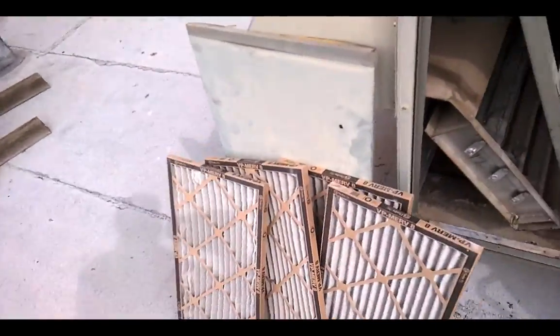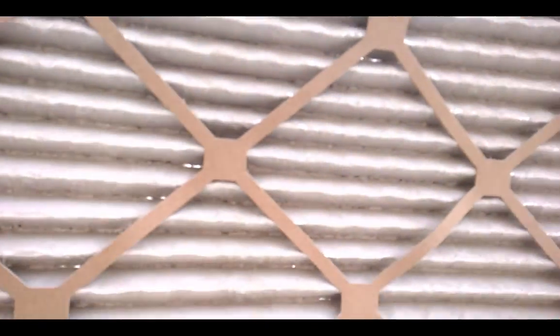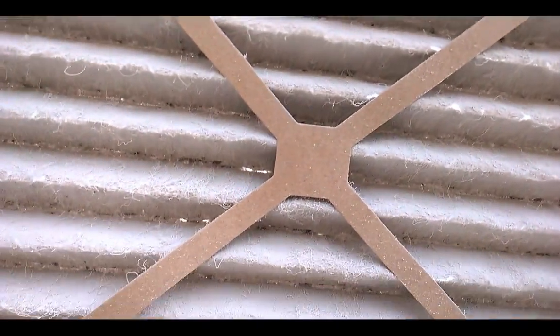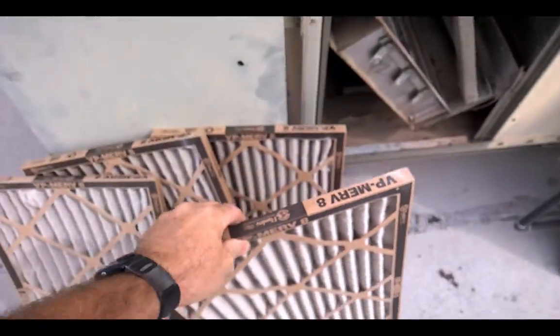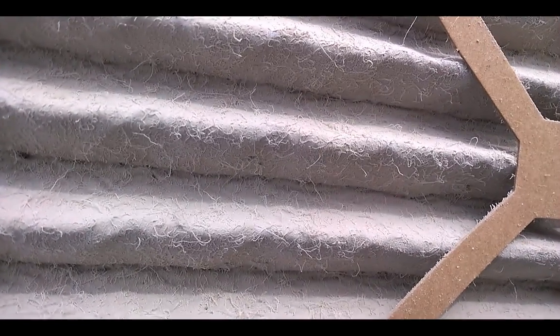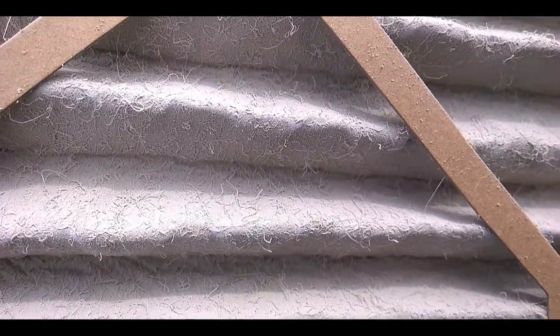I think you need air filters that the air can pass through. Those things are clogged. Looks like some construction drywall dust on this, especially this one. That thing looks alive. That's nasty. Looks like some of it got on the coil in here too.